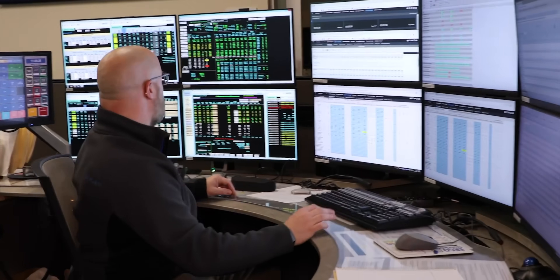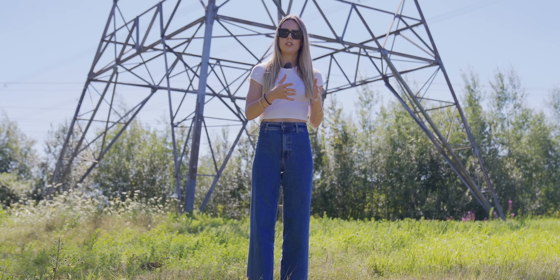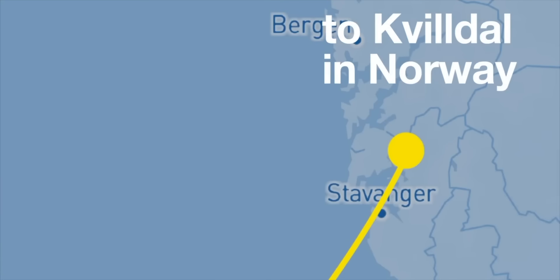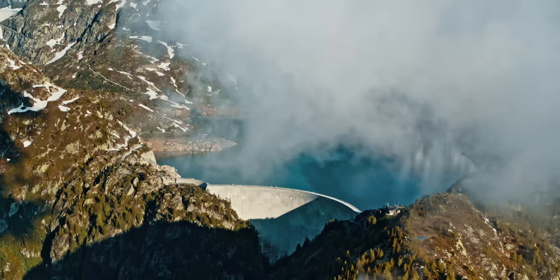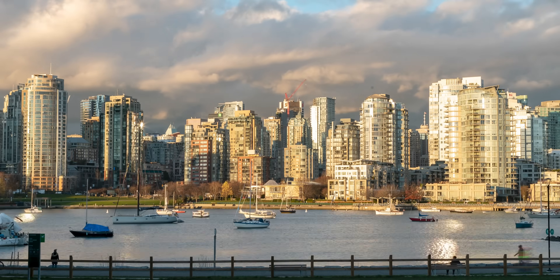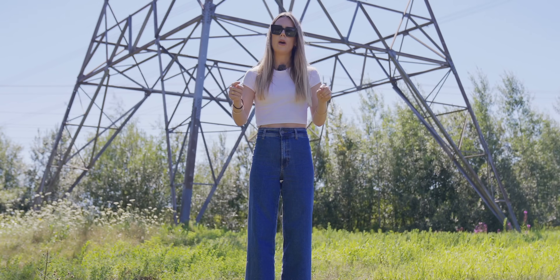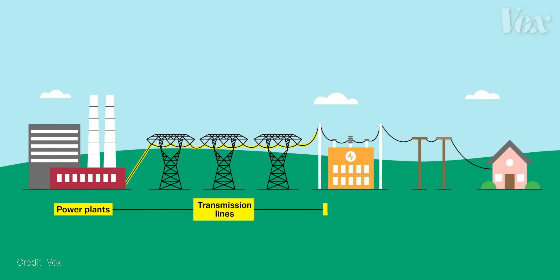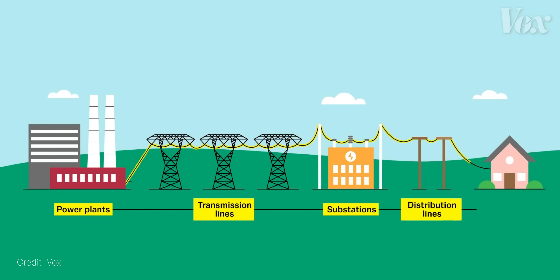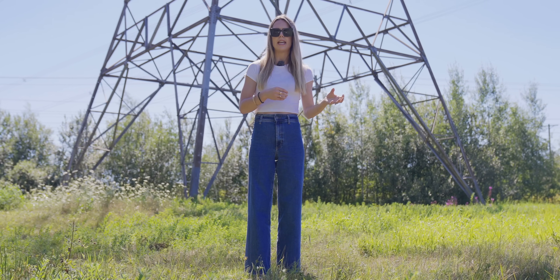When thinking about whether to have AC or DC power lines over long distances, there are a couple of things to consider. In British Columbia it's a slightly different challenge because you've got power being created in pretty remote dams, 700 miles away, but along the way it needs to be siphoned off to support local towns and cities. Every time you have to siphon it off with DC power, you'd have to convert it back into AC and then back into DC, which creates a lot of cost at each substation. So AC definitely simplifies that operation, although there is a trade-off with the losses you get with AC versus DC.